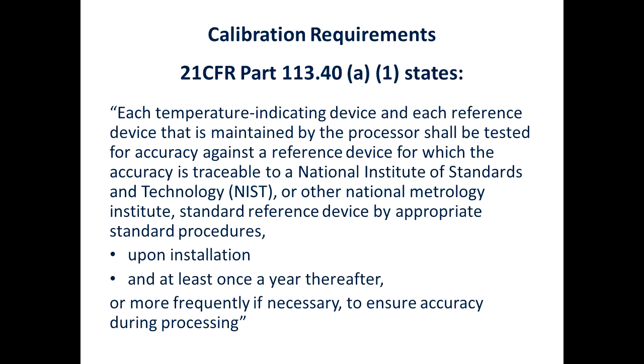If you're using a device and you see that it was to drift out, let's say you had a thermocouple device in there, which is why no one really recommends that, and it drifted over a 6-month period and was out of tolerance, then you would need to pull that device in and calibrate it more frequently. We recommend 1-year calibration on our RTD thermometer system.